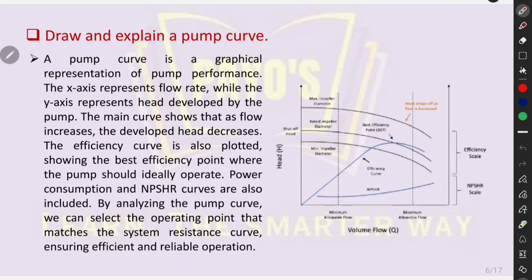Draw and explain a pump curve. A pump curve is a graphical representation of pump performance. The x-axis represents flow rate, while the y-axis represents head developed by the pump. The main curve — the flow versus head curve — shows that as flow increases, the developed head decreases. The efficiency curve is also plotted, showing the best efficiency point where the pump should ideally operate. Power consumption and NPSHR curves are also included. By analyzing the pump curve, we can select the operating point that matches the system resistance curve, ensuring efficient and reliable operation.